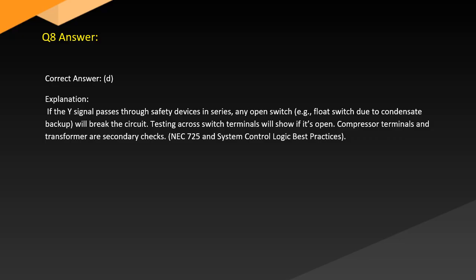Answer. Correct answer: D. Explanation. If the Y signal passes through safety devices in series, any open switch, e.g. float switch, due to condensate backup, will break the circuit. Testing across switch terminals will show if it's open. Compressor terminals and transformer are secondary checks. NEC 725 and System Control Logic Best Practices.